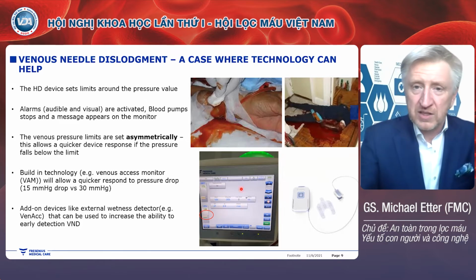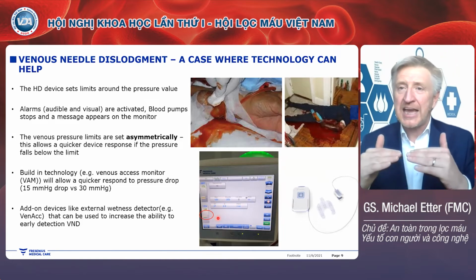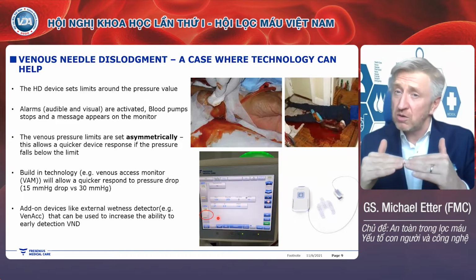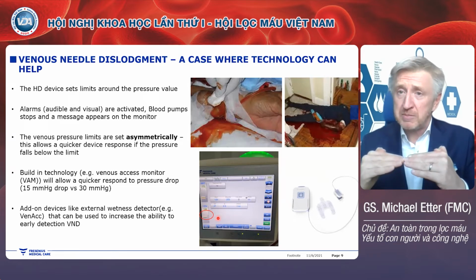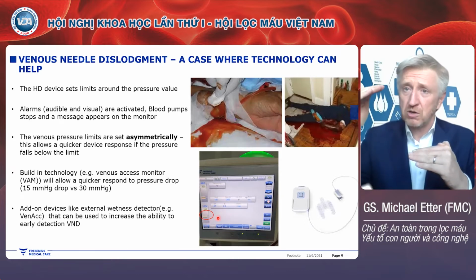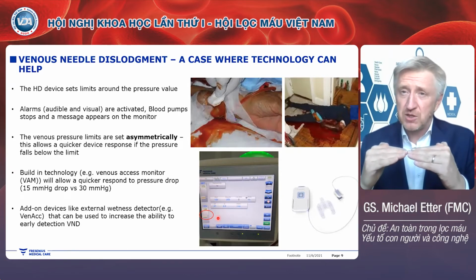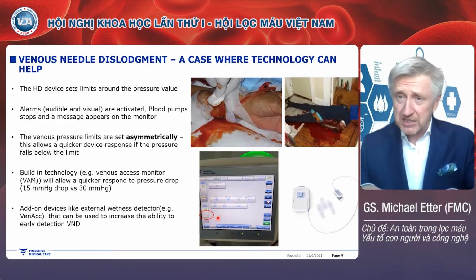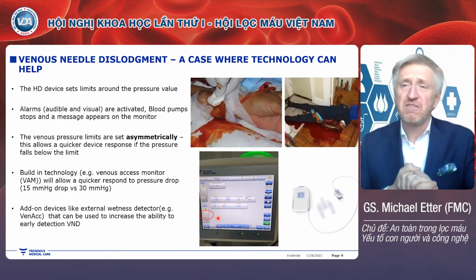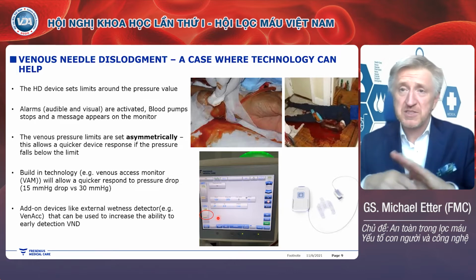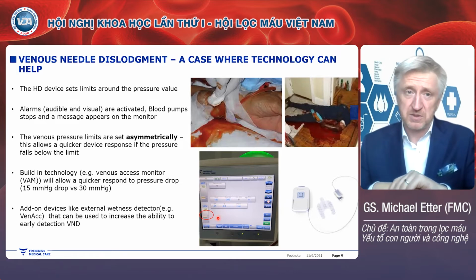You can see here on that little insert where you see the venous pressure alarm, and you see that the error window is the orange part and the green line is on the bottom. The green line, the actual venous pressure, is very close to the low alarm limit of the venous pressure alarm. Not so close to the high, but very close to the low. So if there is a little change of venous pressure downwards, a reduction of venous pressure, you get an alarm. This is a very, very handy concept that we have seen helps a lot in managing venous needle dislodgement.